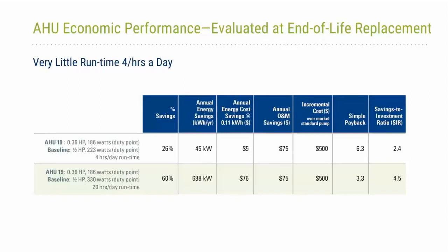We did run another scenario where we were looking at what the energy savings would have been, assuming that it would have run closer to the 20 hours a day like it did when we first looked at it. And then also assuming that the older pump that had failed was still in there. So again, I think if you're comparing this to an old market standard pump that's at the end of its lifetime, you should anticipate getting good savings. If you do have a newer pump that's just a couple of years old, again, your savings are primarily going to come down to the variable speed operation. Okay, next slide.